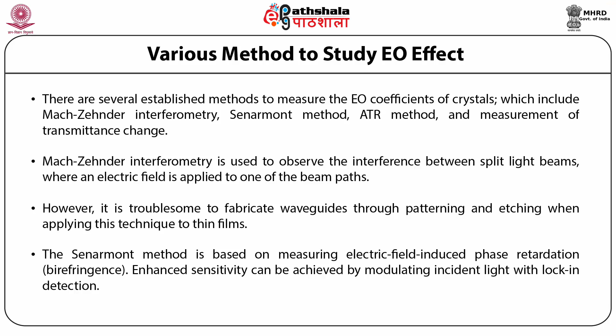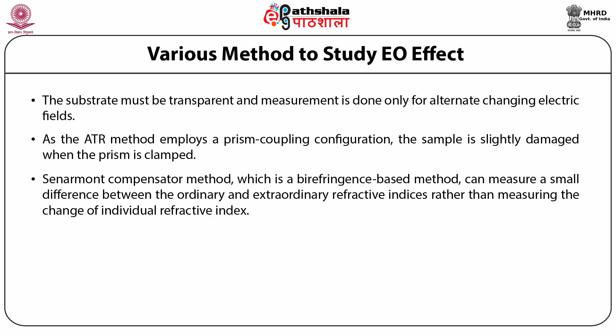Enhanced sensitivity can be achieved by modulating incident light with lock-in detection. The substrate must be transparent and measurement is done only for alternating electric fields. As the ATR method employs a prism coupling configuration, the sample is slightly damaged when the prism is clamped. Another shortcoming common to the above techniques is that the electro-optic coefficient is obtained at a single wavelength of laser light. The Senarmont compensator method, which is a birefringence based method, can measure a small difference between the ordinary and extraordinary refractive indices rather than measuring the change of individual refractive index.